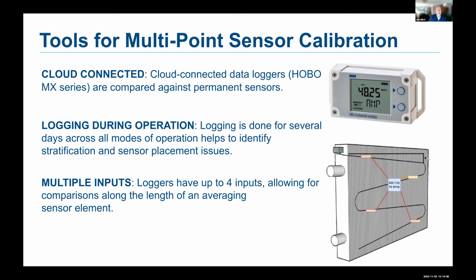So in general, we're using cloud-connected data loggers. We're installing it, in this case, in an air handler, and we're comparing that to the permanent sensors in the equipment. We're doing this over several days and logging across all modes of operation. And what we see is that as the air handler moves into different modes of operation, you can get really significant stratification in the air handler, and you start understanding, are there problems with the sensor placement? Can the sensor where it's installed actually measure things properly according to your sequences? And in general, the loggers have 4 inputs. So you can use them if you have an averaging sensor element across an air handler cross-section. You can be measuring or logging across that entire sensor element.